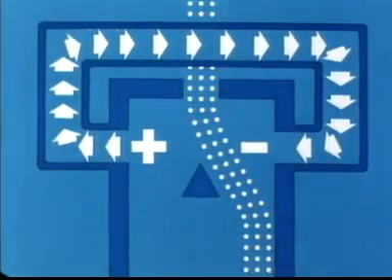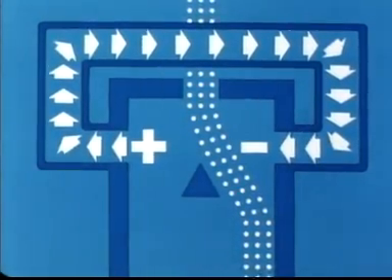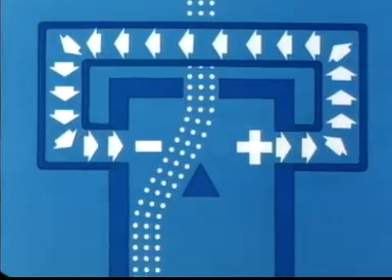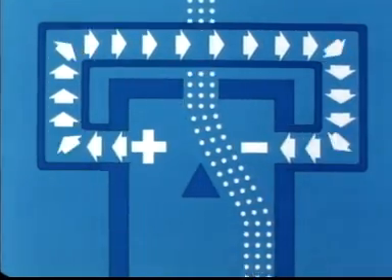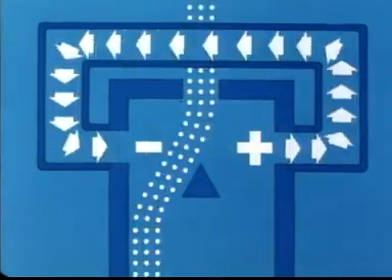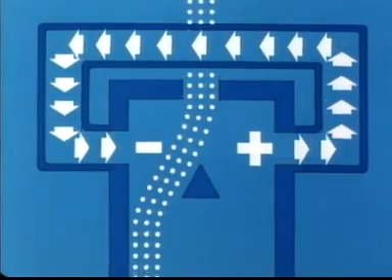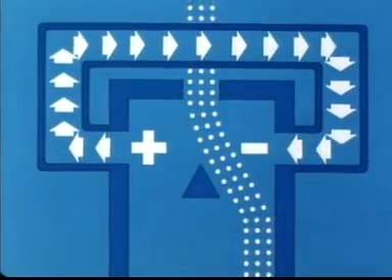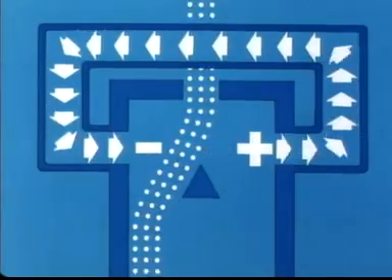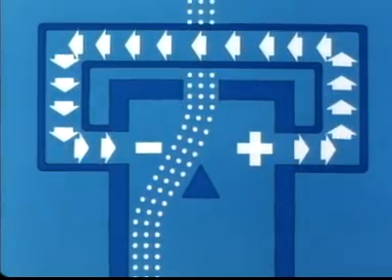The frequency of oscillation is proportional to the velocity of flow. Every pulse represents a specific volume of fluid flowing through the meter. Since the Fluidistor consists of fluid passages and has no moving parts, there's nothing that can sustain wear, and the meter is always accurate.